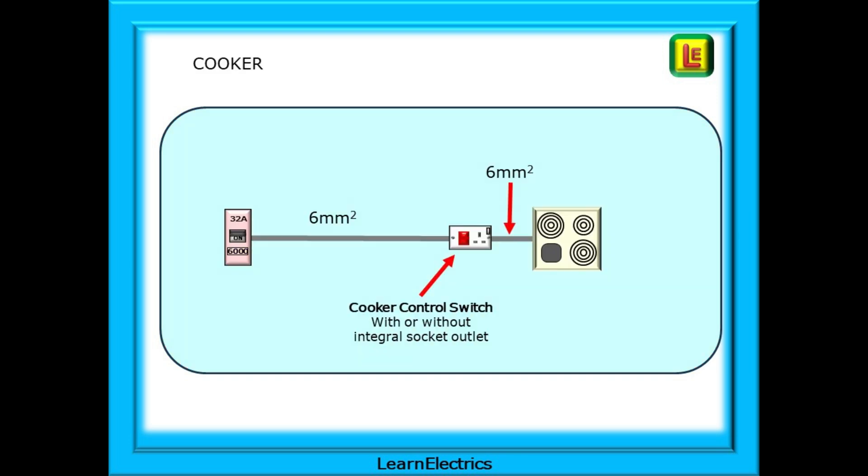The cooker next. The cooker will consume around 30A at full load, not allowing for diversity. So the 32A breaker is more than adequate. Good practice and building regulations recommendations tell us that a 6mm twin-and-earth cable should be used for a 7kW cooker. The circuit should be a dedicated cooker circuit, just for the cooker. A cooker control switch should be installed, which can be cooker only, or have an integrated 13A socket outlet built into it.